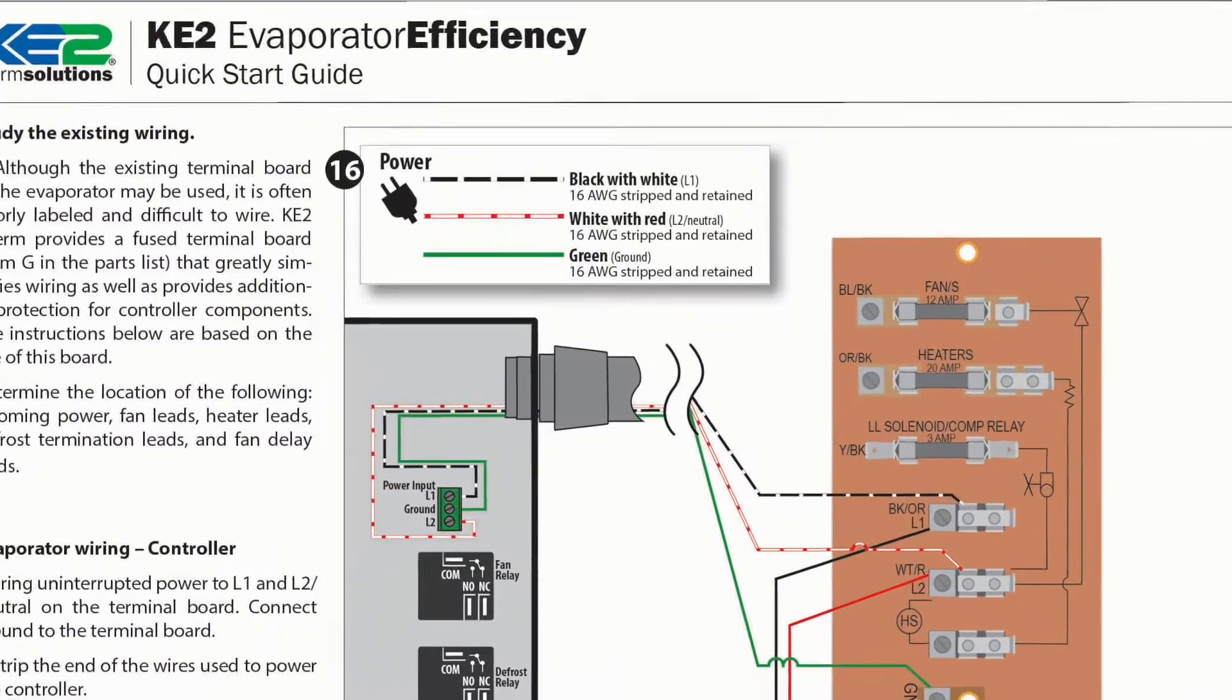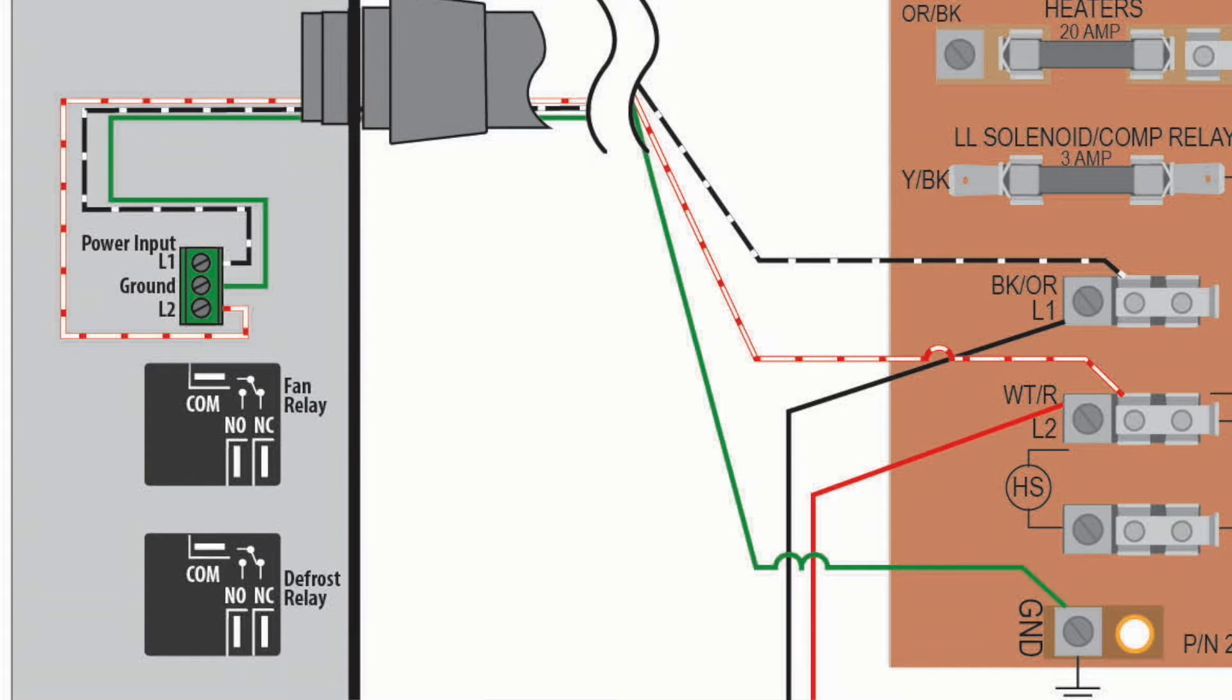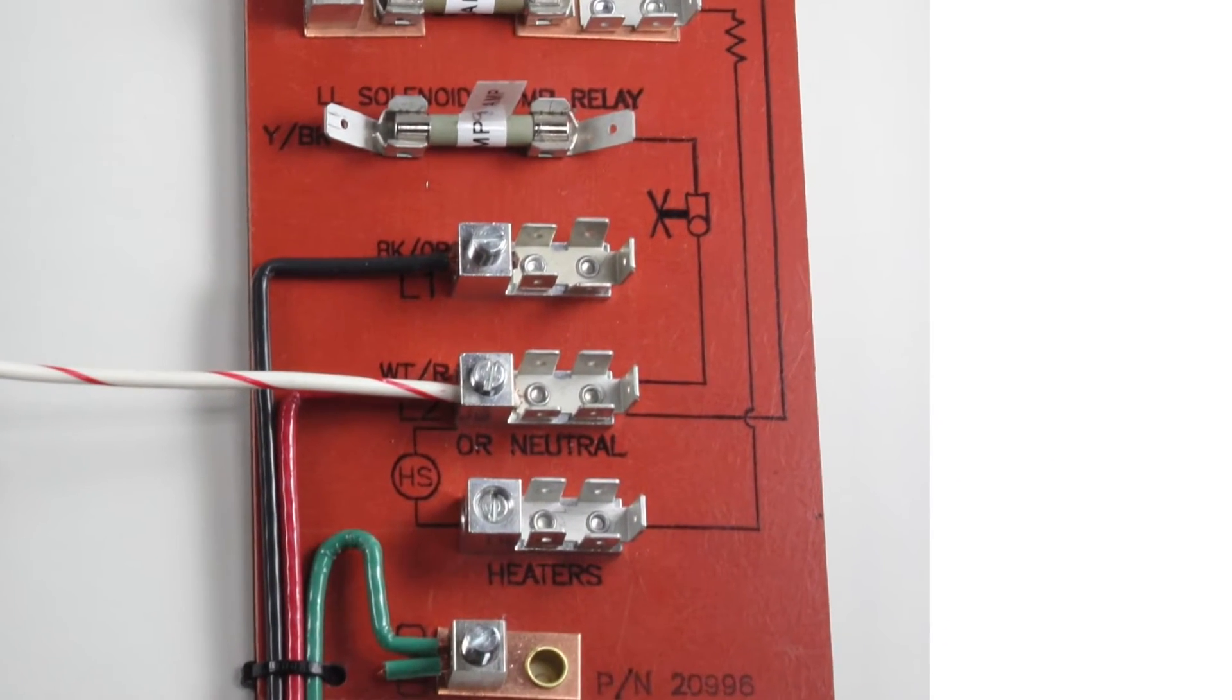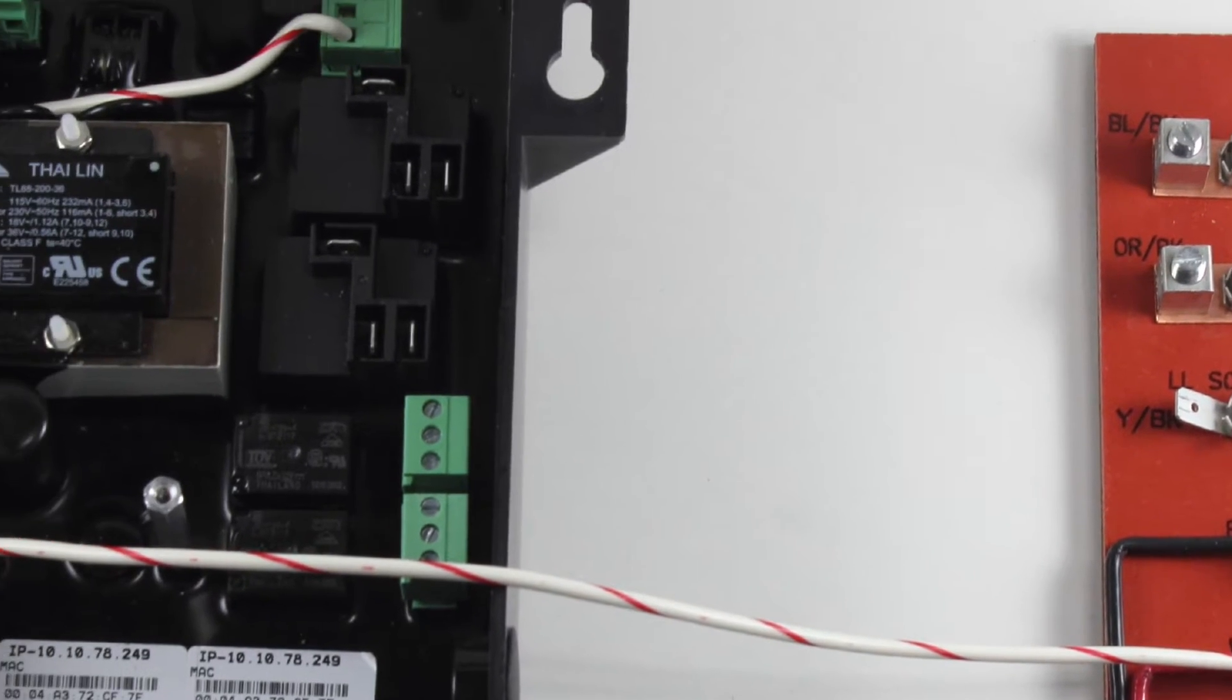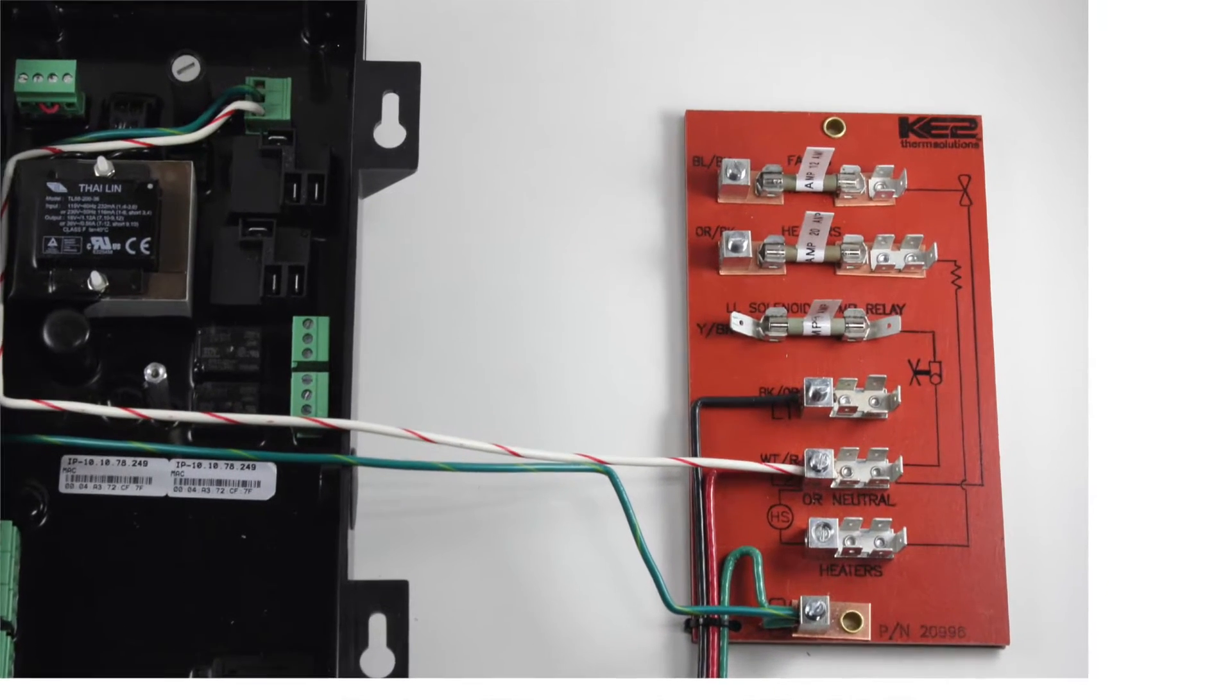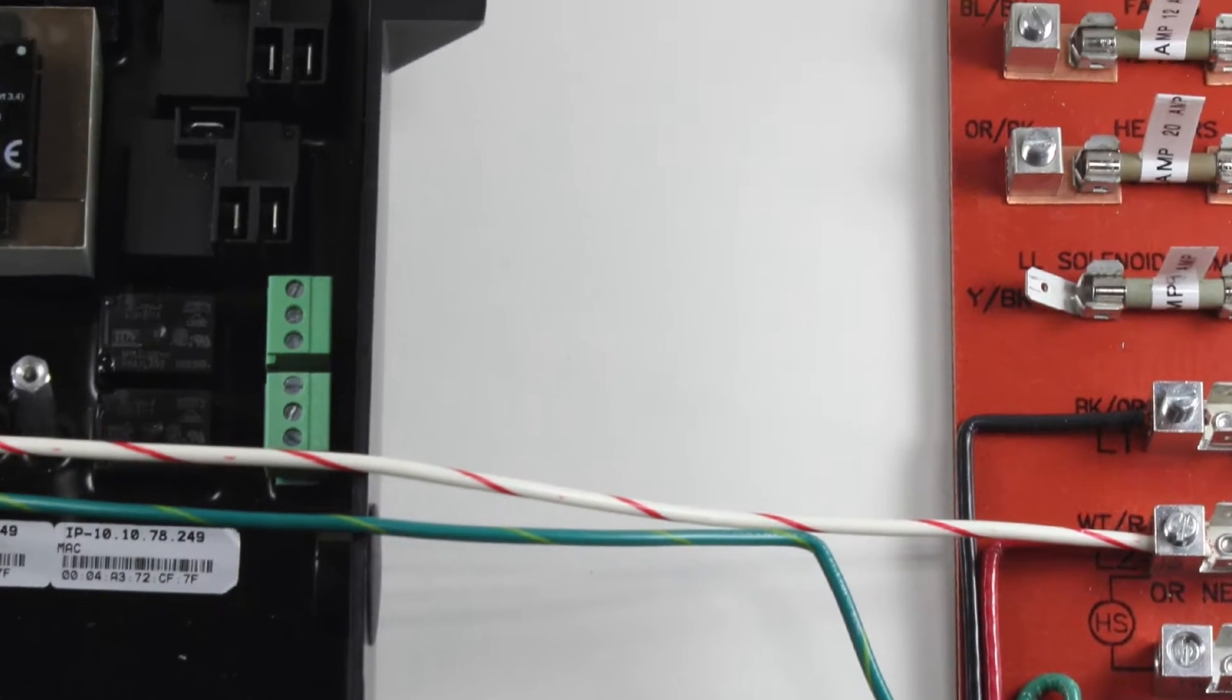The next few steps are to bring the 208 volt power from the terminal board to the controller. Let's begin with line 2 as shown using the white with red stripe. Now, let's connect the ground from the terminal board incoming power to the controller using the green wire.